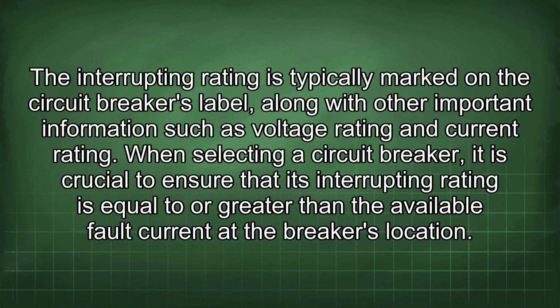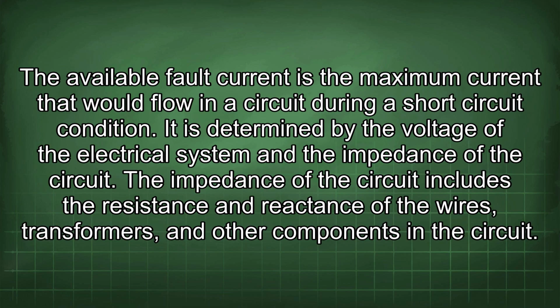The interrupting rating is typically marked on the circuit breaker's label, along with other important information such as voltage rating and current rating. When selecting a circuit breaker, it is crucial to ensure that its interrupting rating is equal to or greater than the available fault current at the breaker's location. The available fault current is the maximum current that would flow in a circuit during a short circuit condition. It is determined by the voltage of the electrical system and the impedance of the circuit.